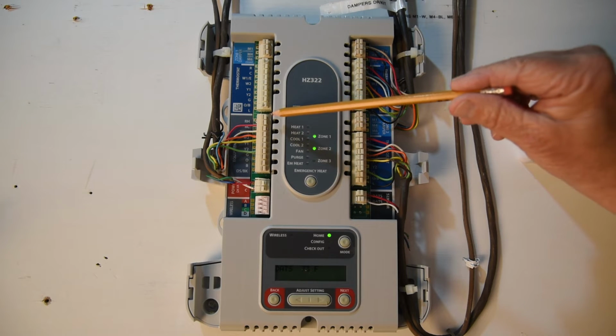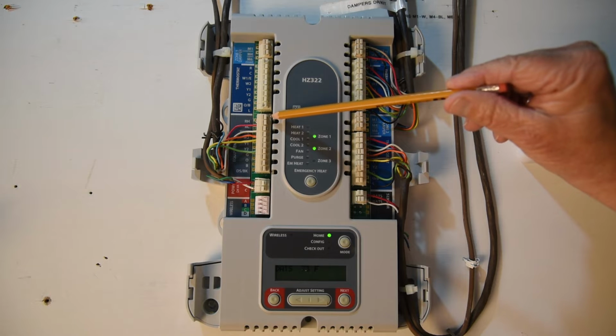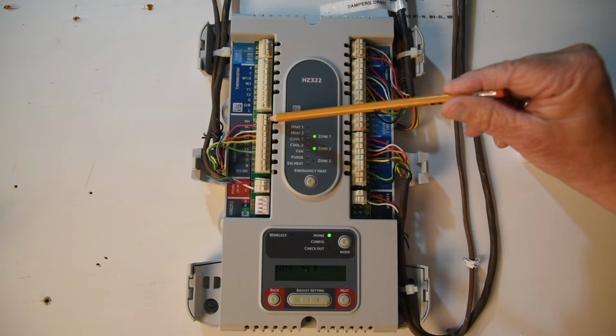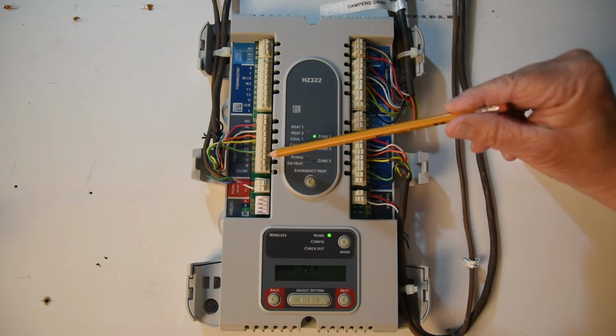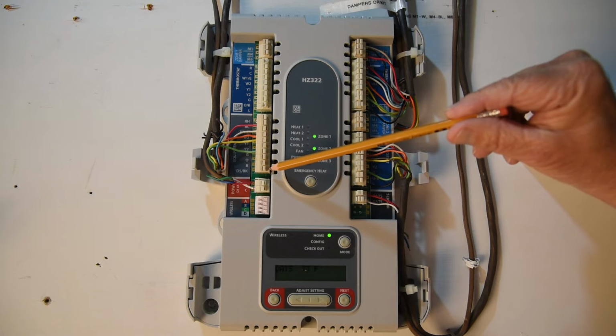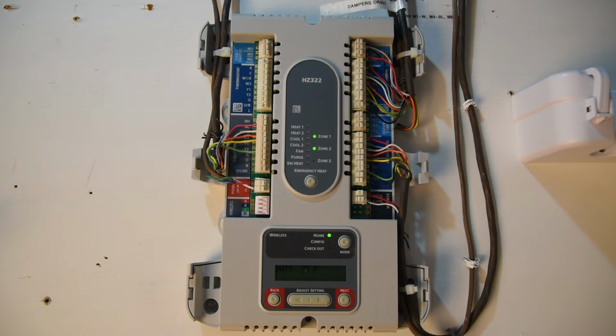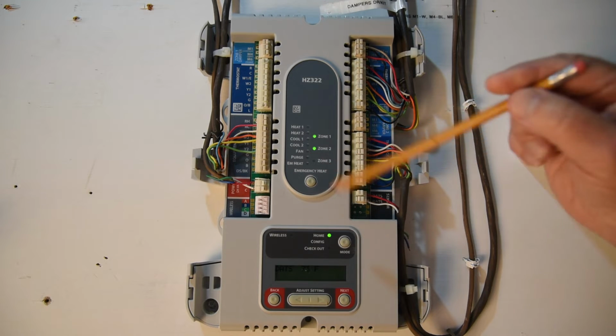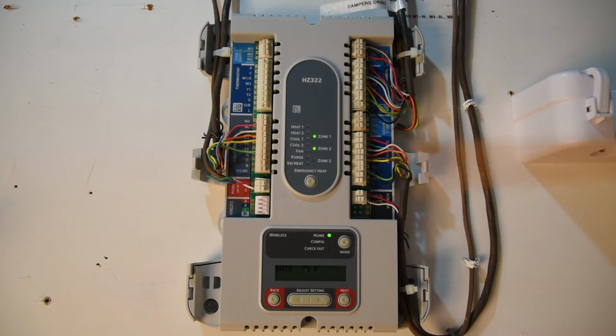Over here on the equipment, that nomenclature is used again on each of the connections. You'll notice that if you have a thermostat that requires a C connection, you will not have a C connection over here. You do not make that connection over to the equipment.